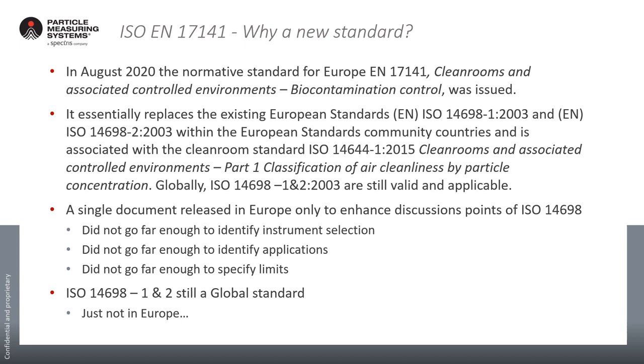One of the reasons they created the new standard was because ISO 14698 didn't go far enough to fully identify instrument selection, didn't go far enough to identify the various applications associated with controlled environments by biocontamination control, and didn't really go far enough to specify limits as to what the expectations were. ISO 14698 parts one and two is still a global standard, just not in Europe.